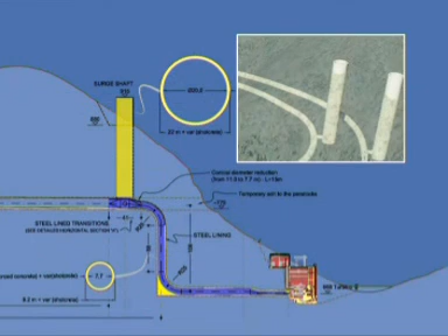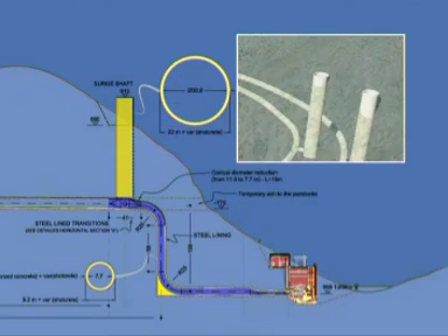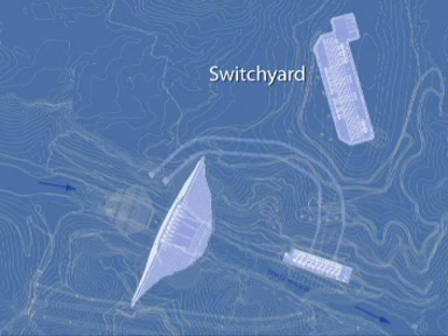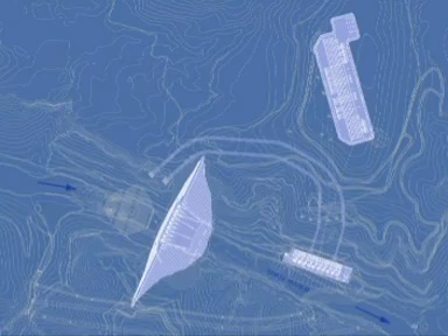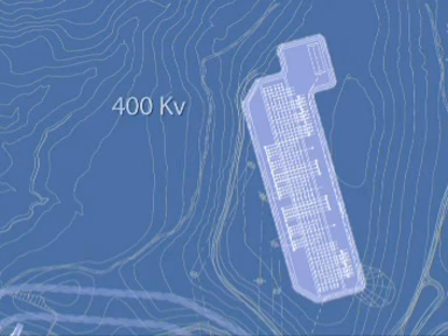2 surge shafts, 130 meters high and 20 meters in diameter, concrete-lined, will be constructed to reduce the pressure in each power tunnel. The power plant switchyard is 400 kilovolt with a double busbar configuration, with 2 halves linked by disconnectors. The switchyard will include 5 incoming bays from the step-up transformers located at the power plant, 5 outgoing line bays connecting the transmission line to the system, 2 coupler bays plus a spare bay ready to accommodate future extension.